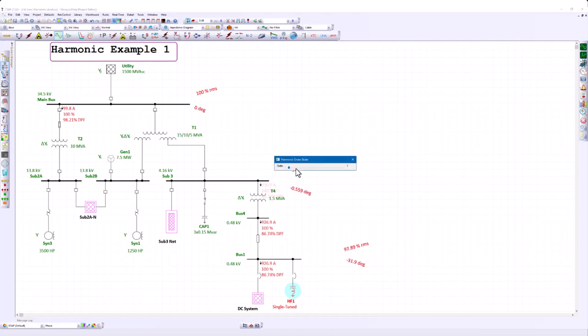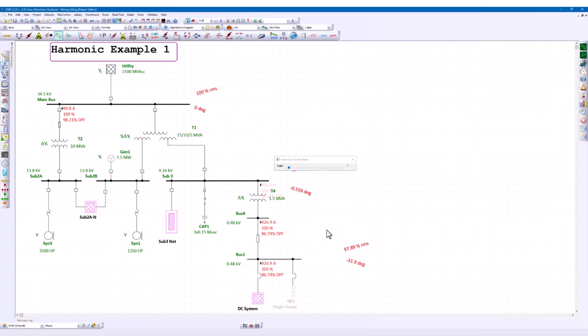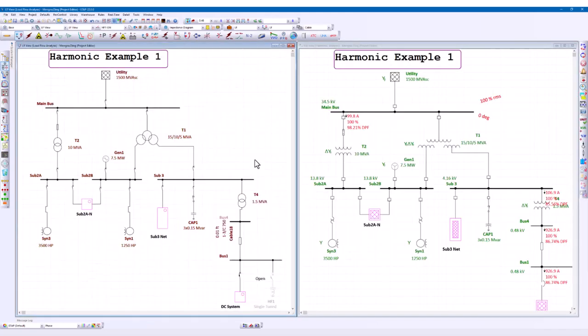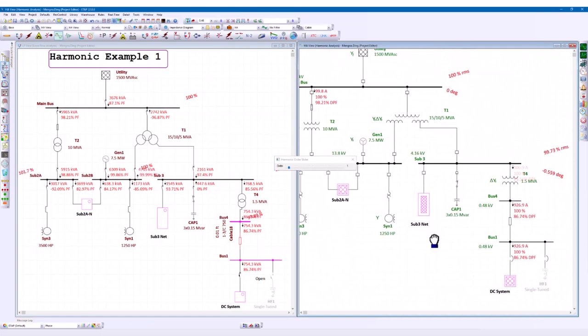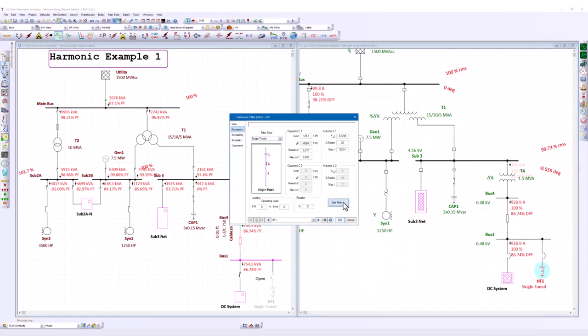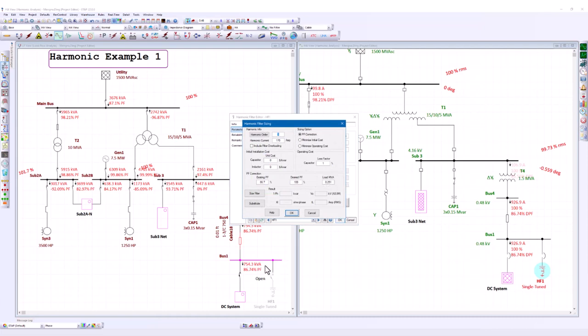Let's move the order slider to the fundamental, or the first order. You will notice that the power factor without the harmonic filter is 86.74. In order to find the connected load, let's set up another presentation and run a load flow calculation. Now I have another presentation for running a load flow. Let's run load flow, and we are able to see the total kVA flowing into bus 1 is 754 kVA. To size a filter, we need the per phase operating load. So the per phase load would be the number we read from the load flow calculation divided by 3, which is 251. So now I have all the information needed for doing a filter sizing.